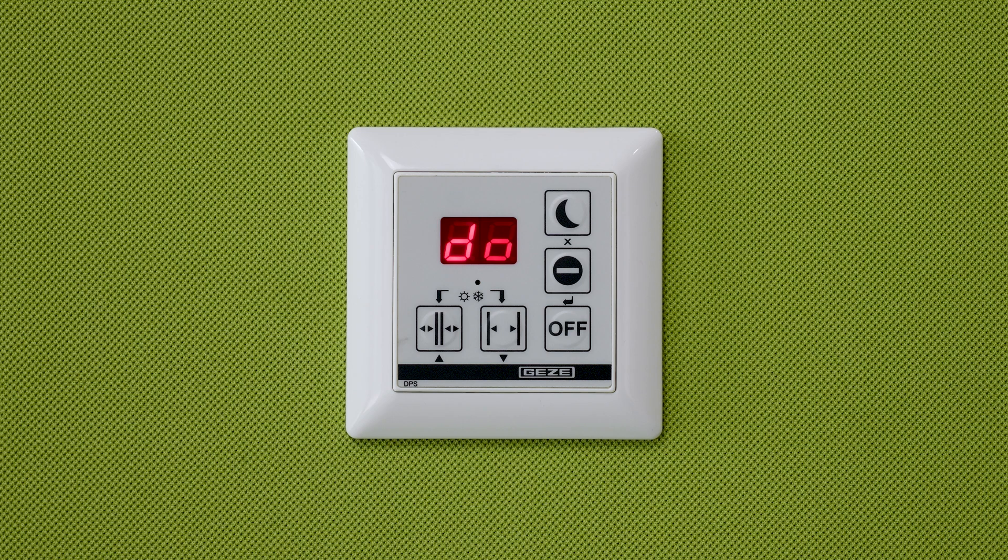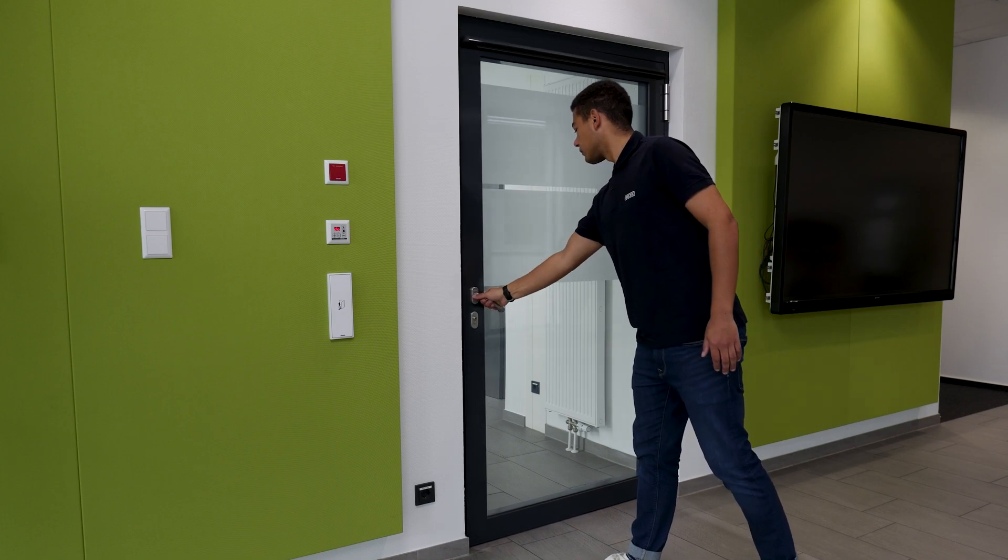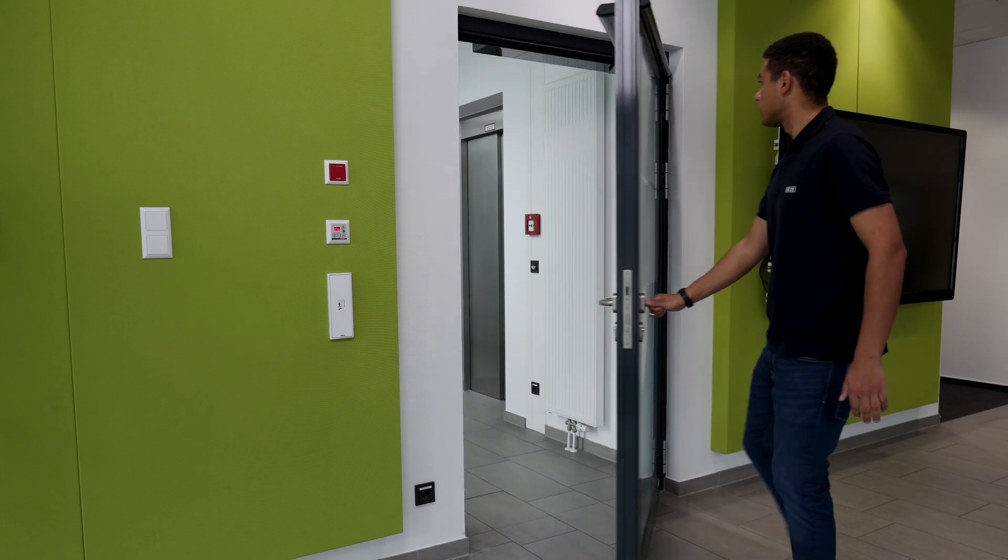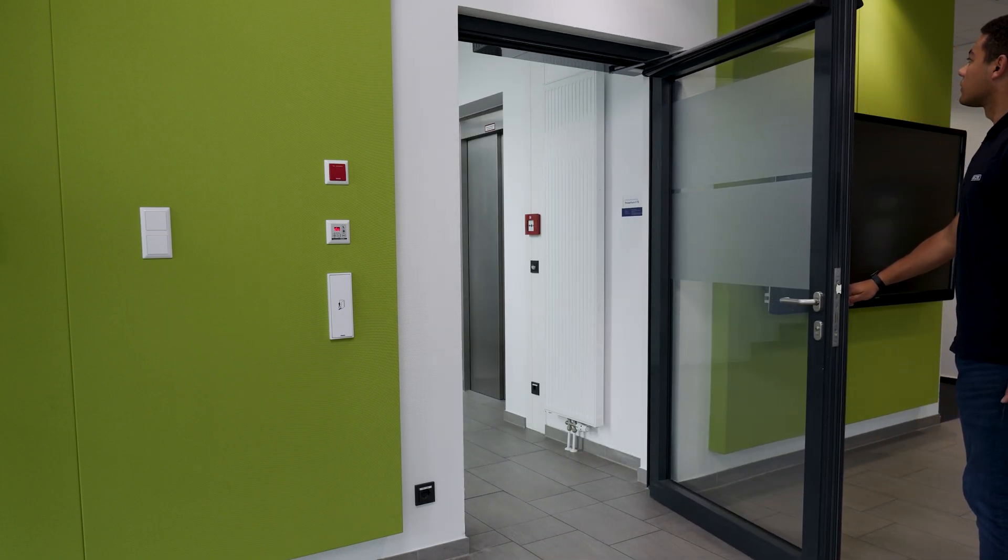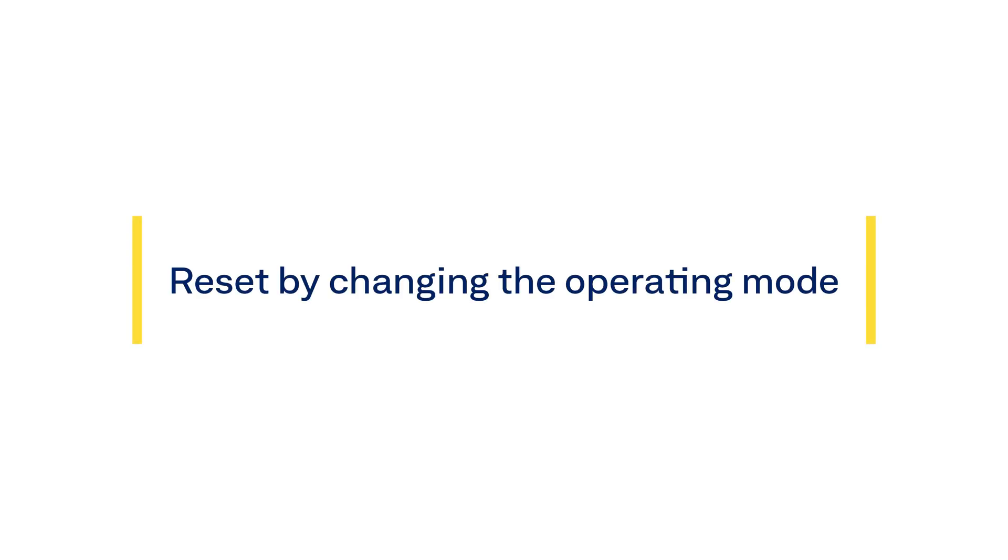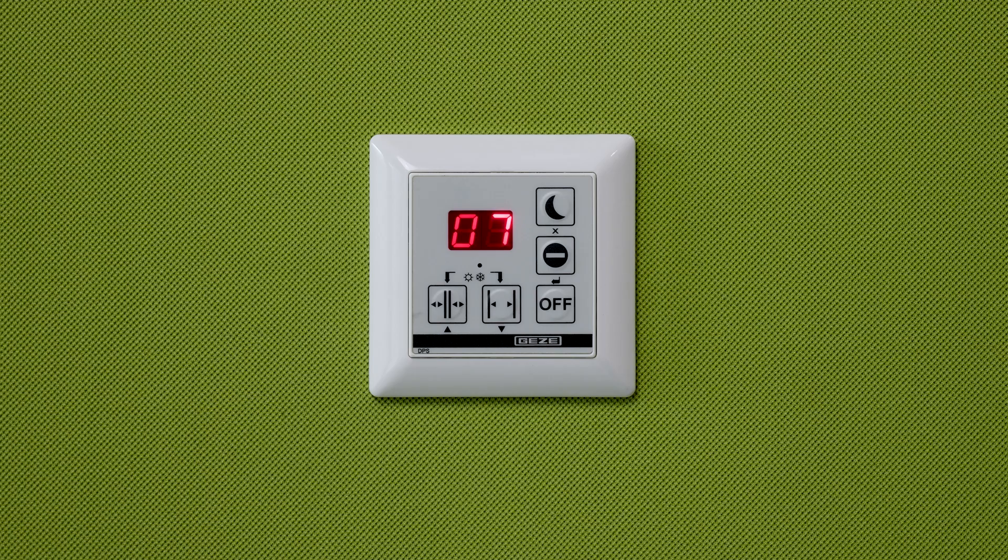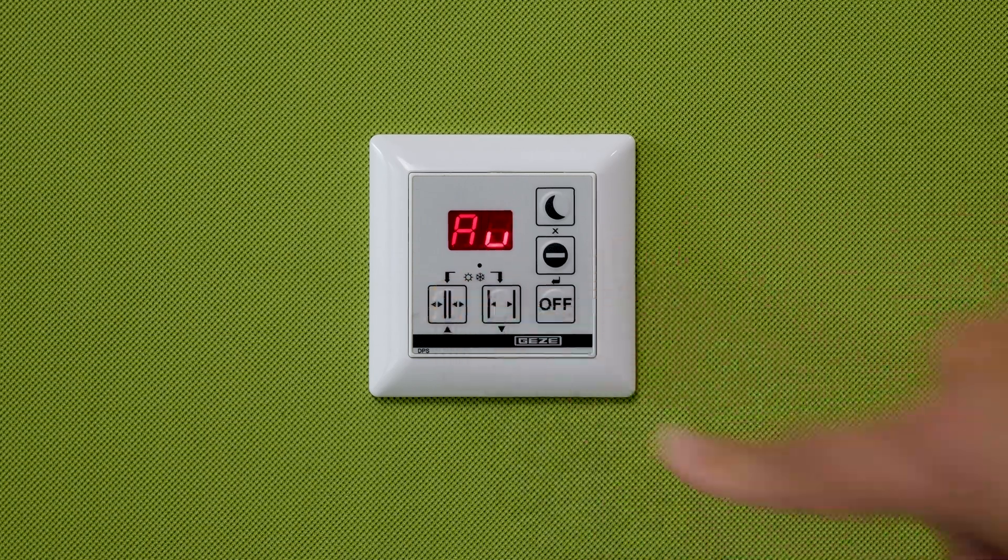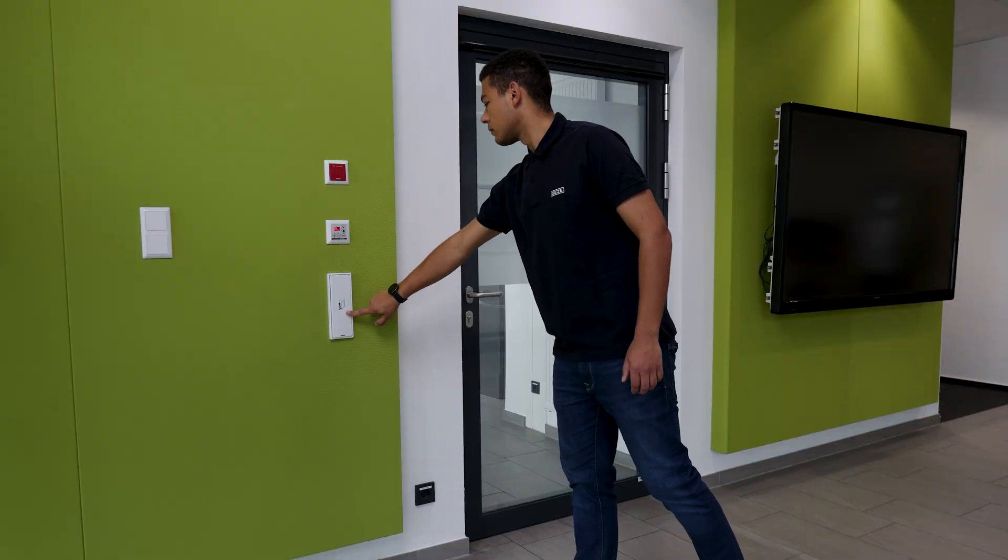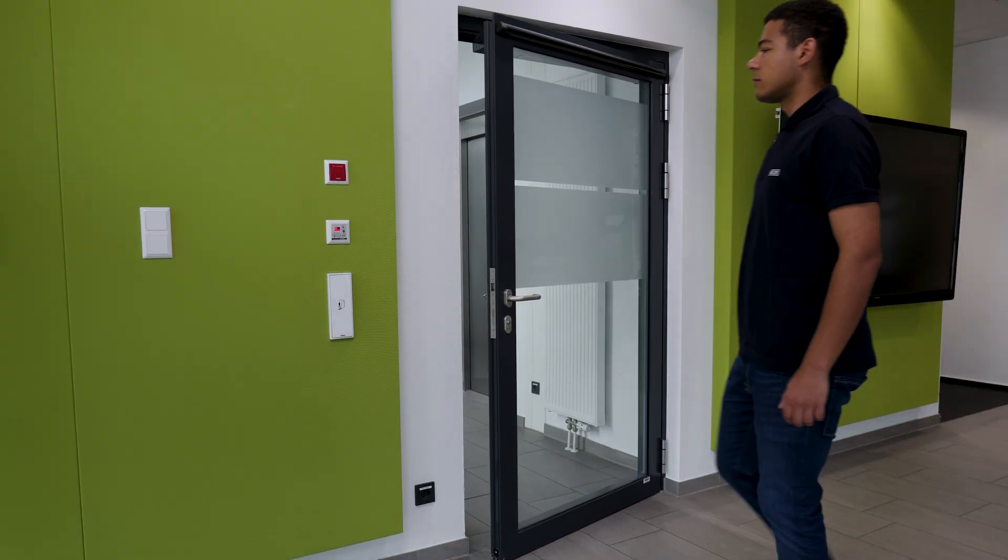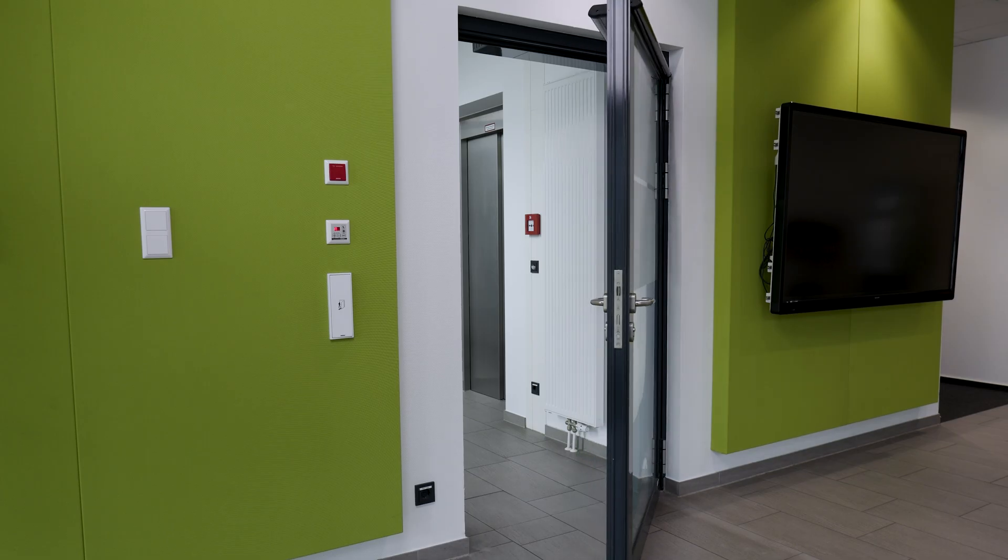A reset is required on site to enable the drive to operate automatically again. The manual reset is performed by opening the door by at least 80 degrees. Regardless of the setting, the reset can always be performed by changing the mode of operation on site.